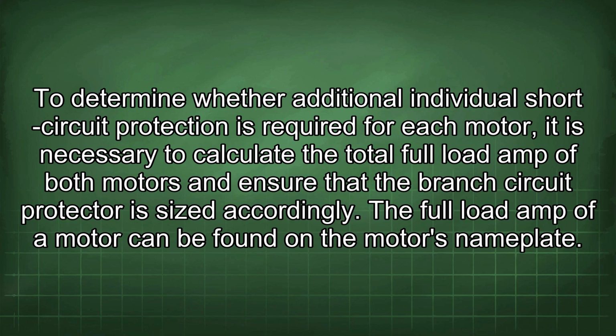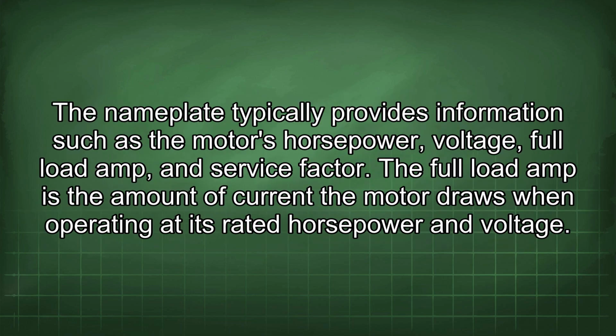The full load amp of a motor can be found on the motor's nameplate. The nameplate typically provides information such as the motor's horsepower, voltage, full load amp, and service factor. The full load amp is the amount of current the motor draws when operating at its rated horsepower and voltage.